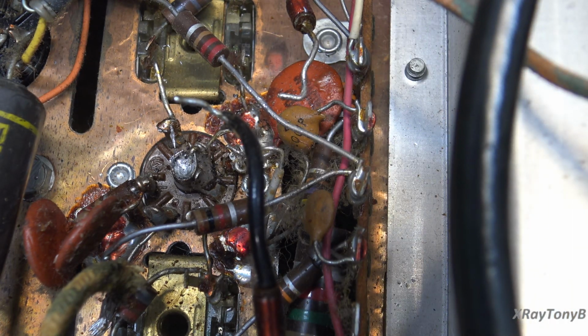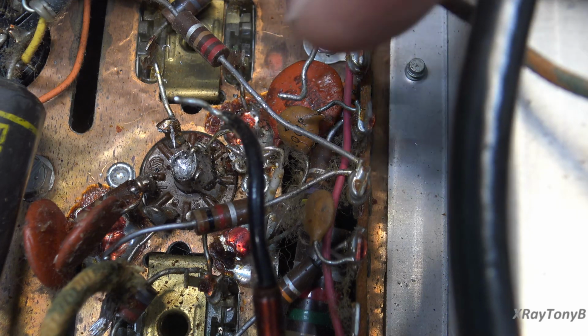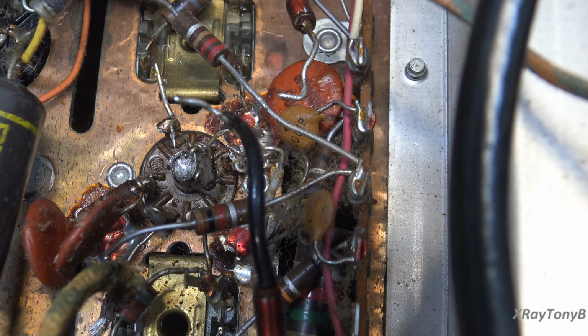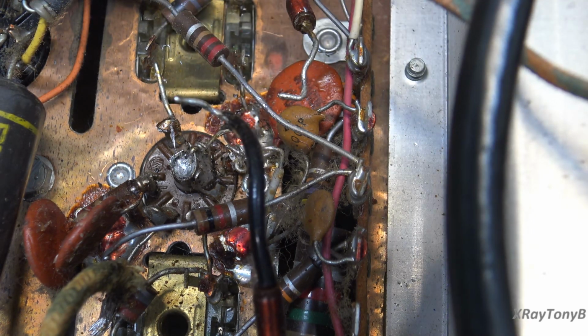So who knows? Now, I never touched anything over there, so I don't believe I introduced that short. I kind of believe that's been like that for a while and probably was intermittently causing problems with this for some time. And that might be also why somebody had replaced the fuse with a 4 amp fuse, because this was probably just barely touching in here for a long time, and it was probably just enough resistance to blow the 2 amp fuse, so somebody replaced it with a 4 amp slow blow fuse.